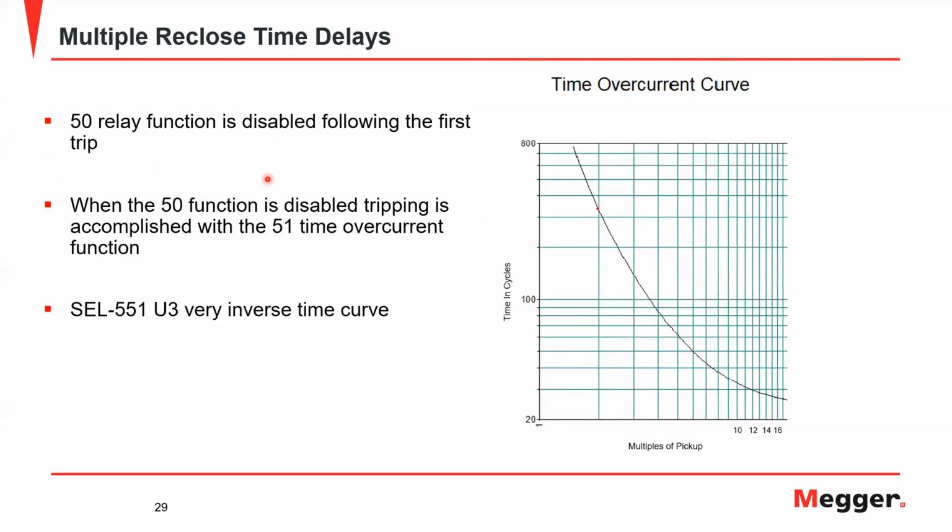So now let's look just a little bit at the overcurrent relaying. Now, David Beard just earlier today talked a good bit about overcurrent relaying, so I'm not going to go over this too deep. I'm going to focus on how it impacts reclosing. Just a little bit about the time curve here, and this is actually the time curve of the relay that I'll be testing here shortly, and this dot is a predicted trip time for the fault current that I'll be applying.